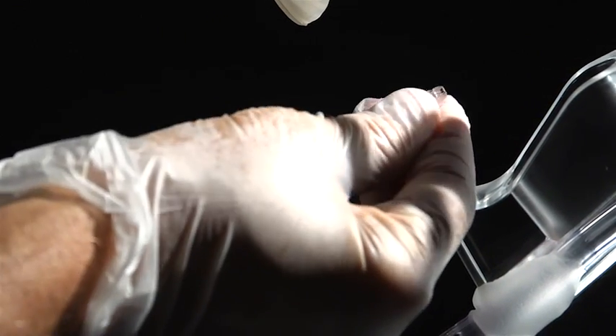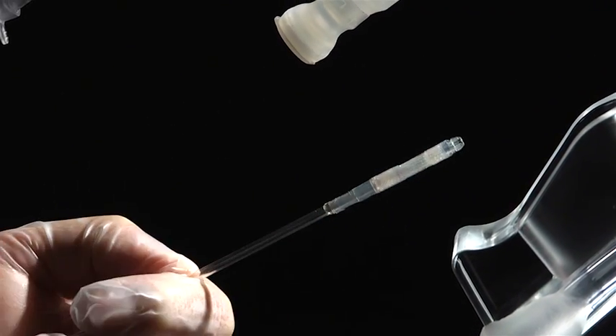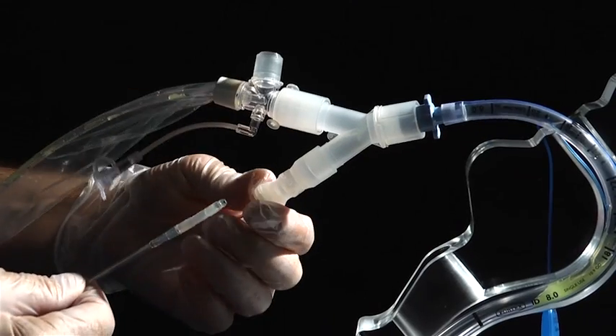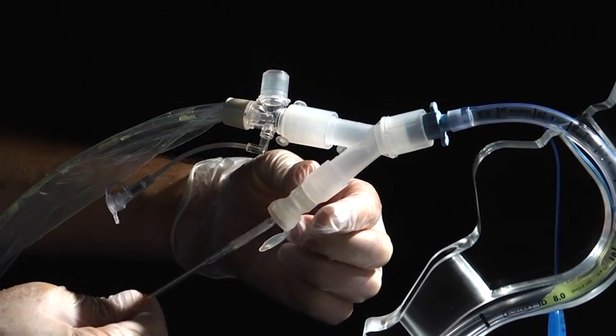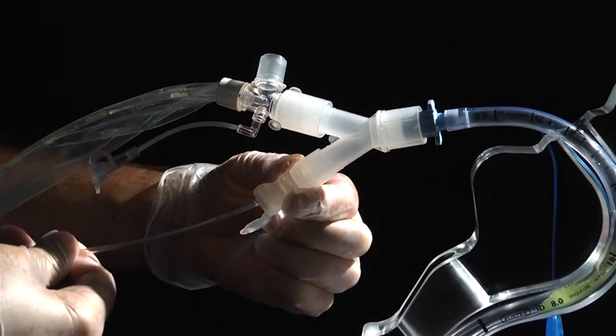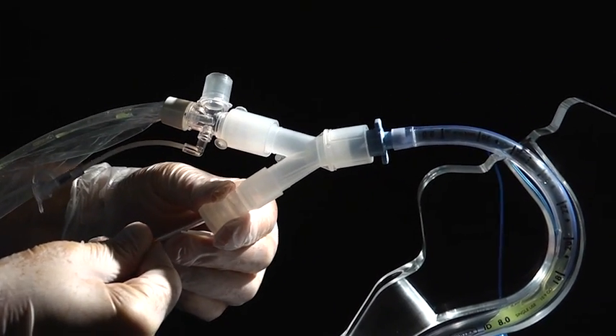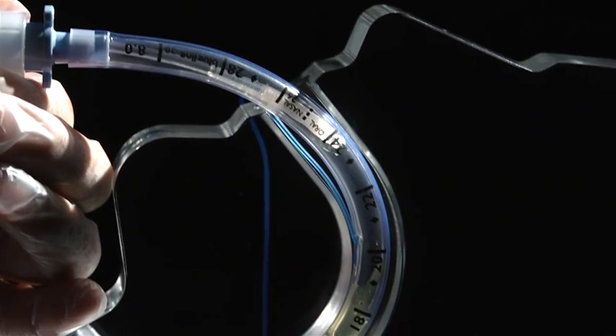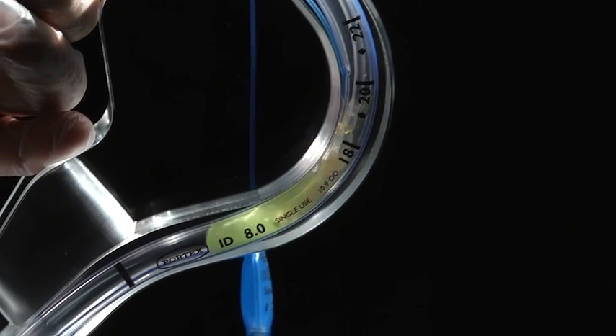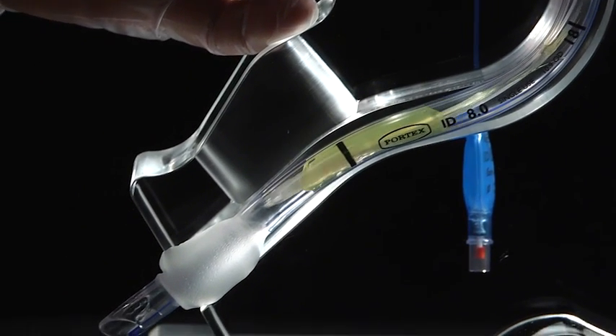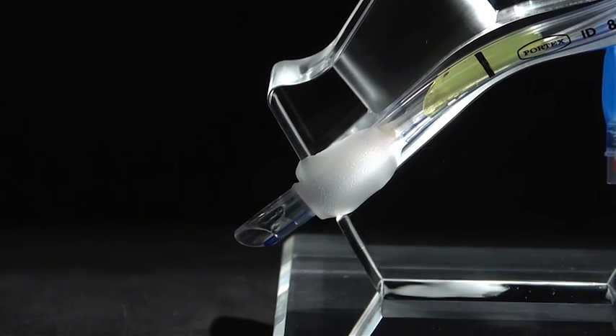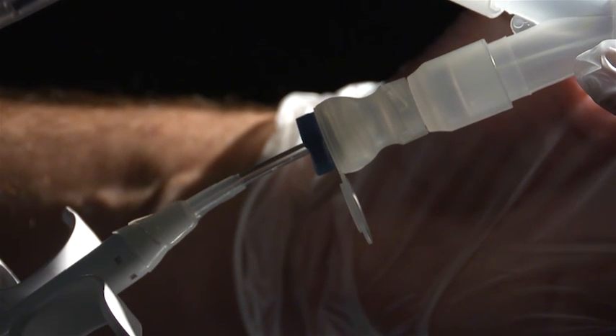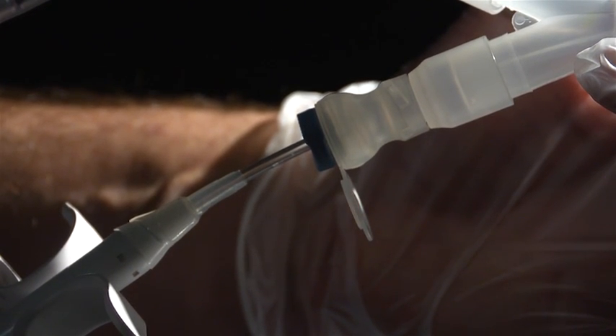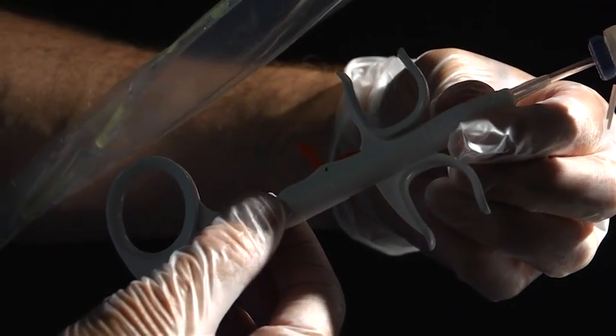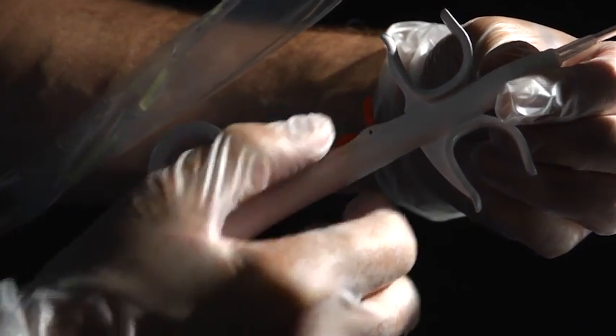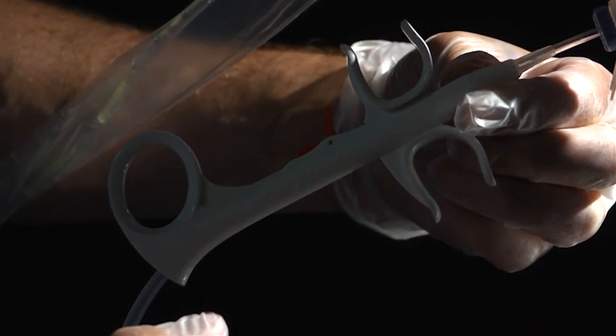A small amount of surgical lubricant is placed on the tip of the endOclear device. Next, the endOclear device is inserted into the BCA adapter. The endOclear device is then inserted into the endotracheal tube. You see it passing through the secretions, and it's placed up to the blue stop. Once the device is positioned according to the depth marker, the safety toggle is released, which allows us to deploy the cleaning member.